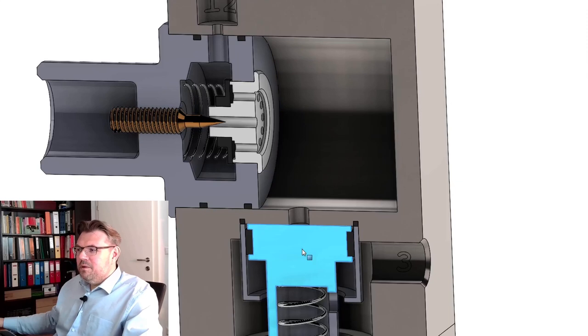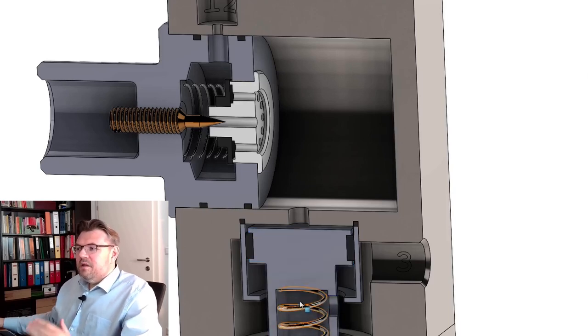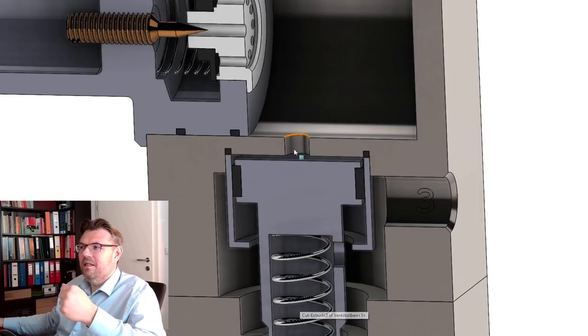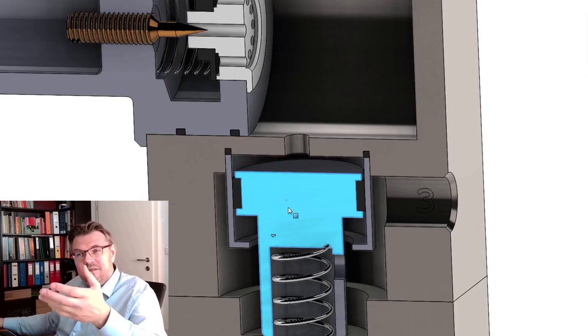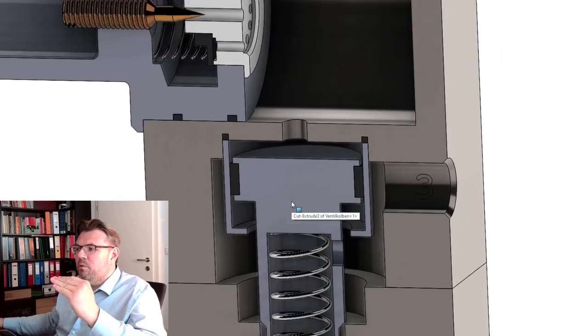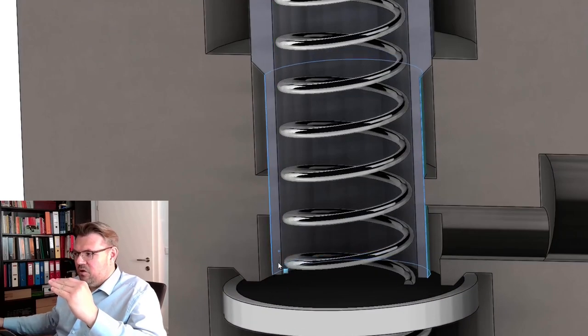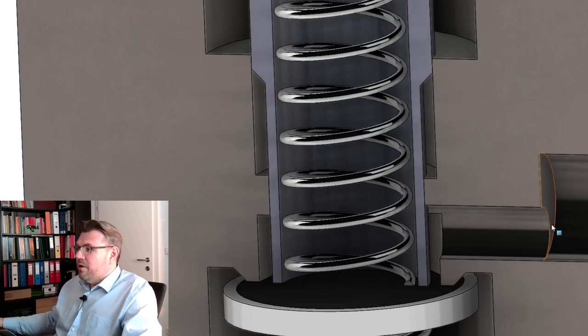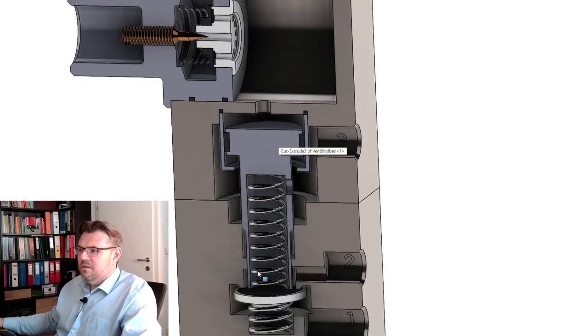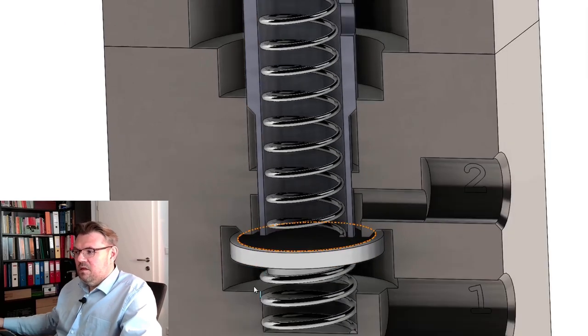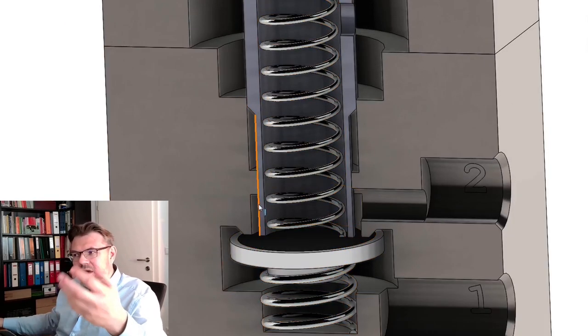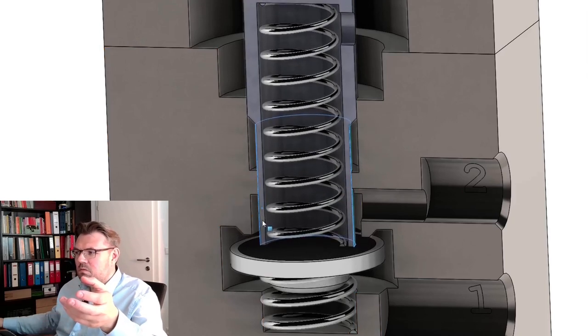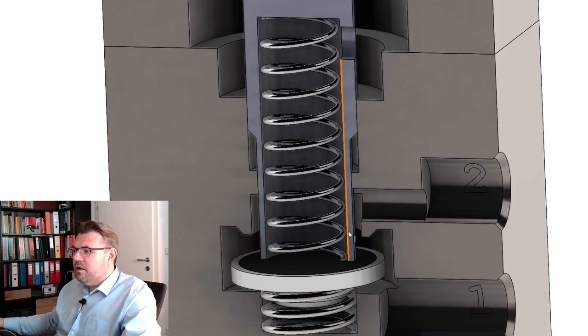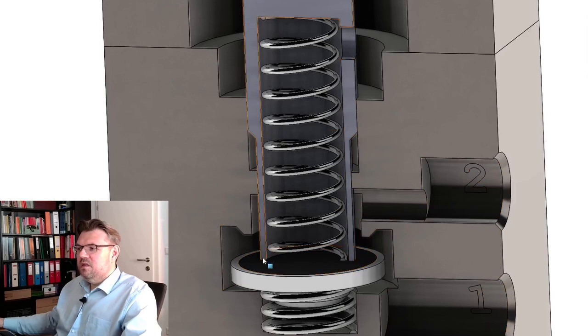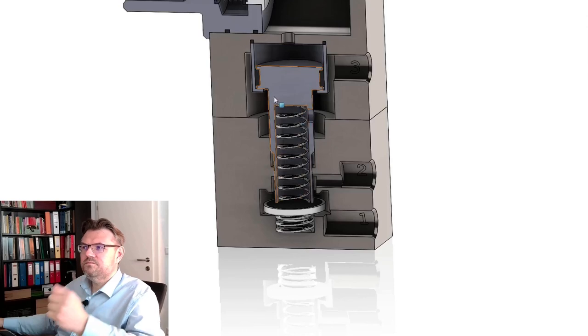If we build pressure here, we will start up to pull this down against the force of this spring. However, it takes simply a while. And then it will expand, even if this is going down, it will expand and again take some time, and it will slowly push down this. And at a certain point in time, we will separate the 2 connector from the 3 connector. However, this will not stop pushing. This is an even bigger spring here, so we need more force, so we apply more pressure above, and it again takes a while, and then now we are opening 1 and 2. Okay, now 1 and 2 are interconnected to each other, and here is sealed, so we are no longer connected to 3. This took a while.